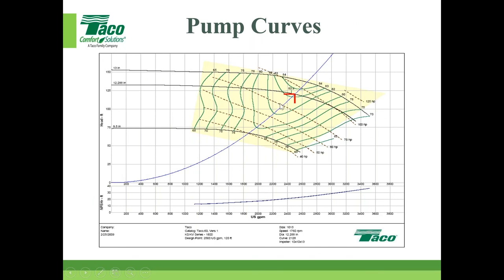We have our range, and the horsepower lines are usually curved in this direction. They come down here, they're usually dotted, right? And then your impeller max and the minimum, the actual. And nowadays, most manufacturers show you the actual design point with the system curve going through it. And then your NPSH is shown down here in the bottom. So it's pretty standard information on these curves.